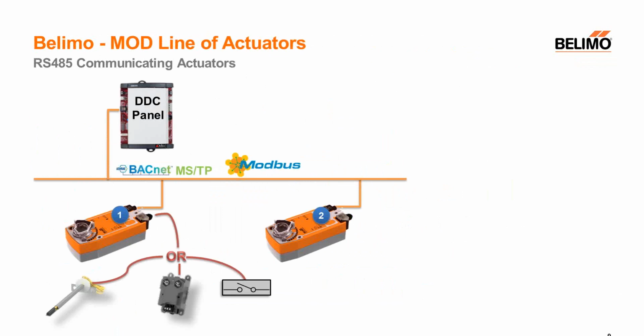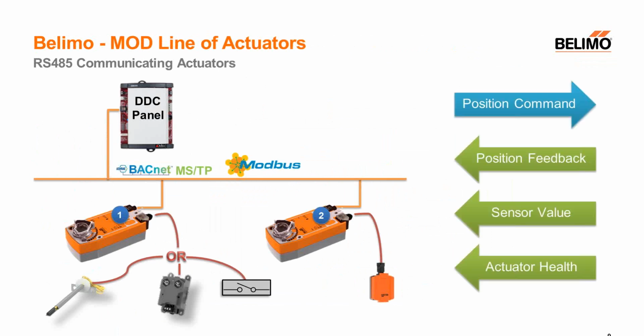The actuators also have the ability to hook sensors up to them. One input on each of these actuators allows you to hook up a passive sensor, an active sensor, maybe a pressure or humidity sensor, or a dry contact closure, which could be a freezestat or something like that. And we always appreciate when you use the orange sensors to connect to them as well. But each one of those actuators allows one sensor.